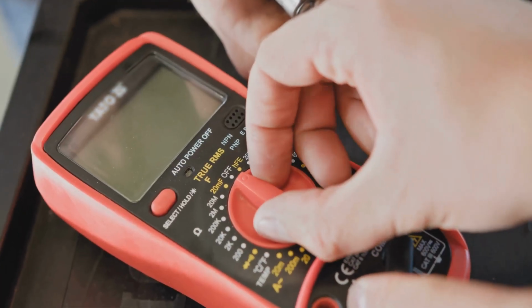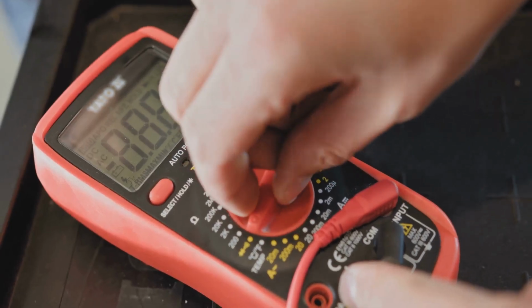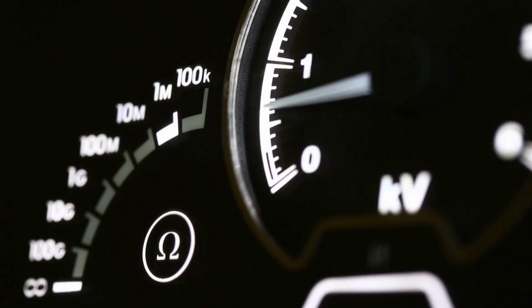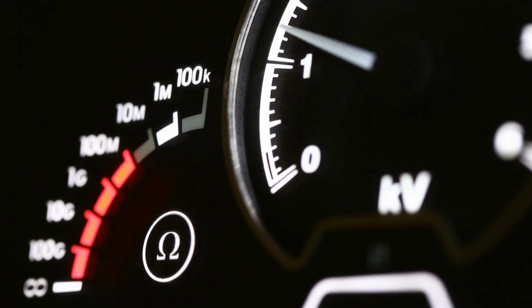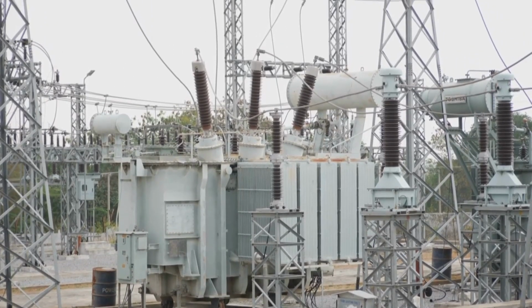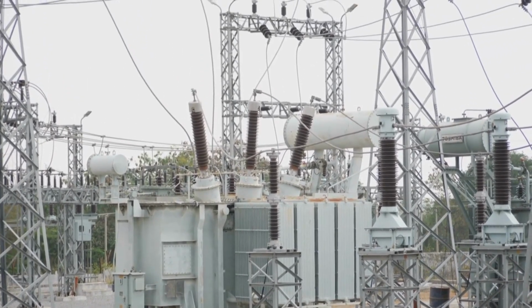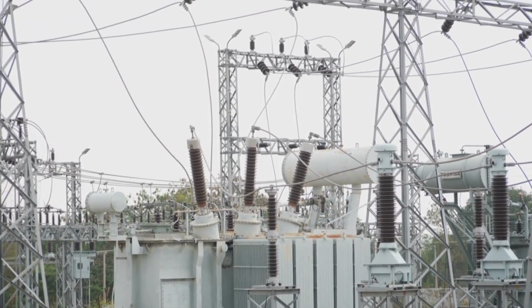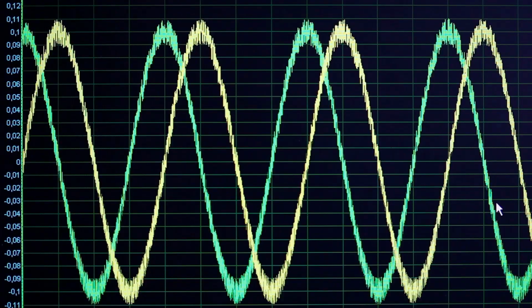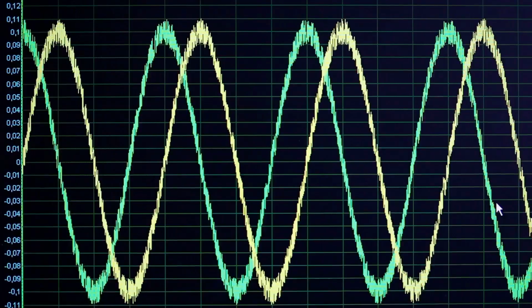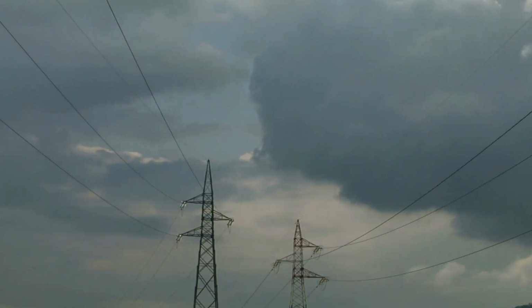Clause 4.1, Voltage and Frequency Ride-Through Boundaries. This clause defines the normal operating voltage range, typically 88 to 110% of nominal, and frequency range, 59.3 to 60.5 Hz, at which DERs must remain connected. But more importantly, it sets the stage for when a DER must not disconnect during abnormal, but still tolerable, grid events. In other words, when voltage dips to 90% for a few cycles, or frequency sags to 59.5 Hz, the DER must stay online and support recovery. This is the core definition of fault ride-through.